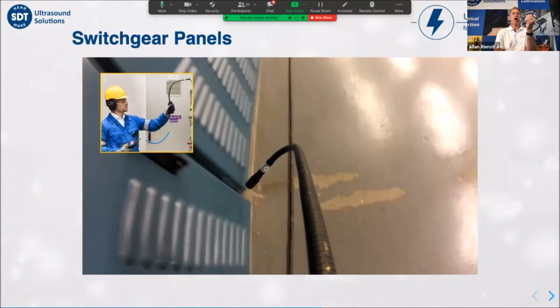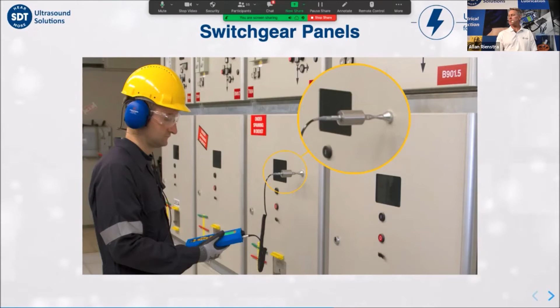Now, when we come across a panel that is hermetically sealed, we simply place a contact ultrasound sensor with a magnet directly on the cabinet's outer panel. Any ultrasound inside that panel will do one of a few things: some hits the panel and reflects back in, some is absorbed by the steel panel, and some passes through the steel panel and into our sensor, allowing our inspector to hear it. Think about when you visit your doctor and they put a stethoscope on your chest to listen to your heart - it's exactly the same concept, the same principle.